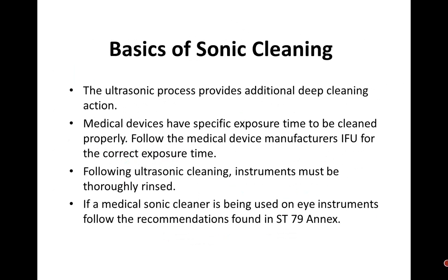Now back again, you want to use detergent formulated specifically for medical ultrasonic cleaners. That is very, very important. You don't want to pull something that isn't made for it, because the detergent itself decreases the surface tension within the solution, and that helps the cavitation process. So you want to make sure you're using detergent that is specifically designed for sonic cleaners. The cleaning solution in the ultrasonic should be changed whenever it is visibly soiled, at least once or twice a shift. It's very subjective. Follow the IFU for your detergent and the sonic.